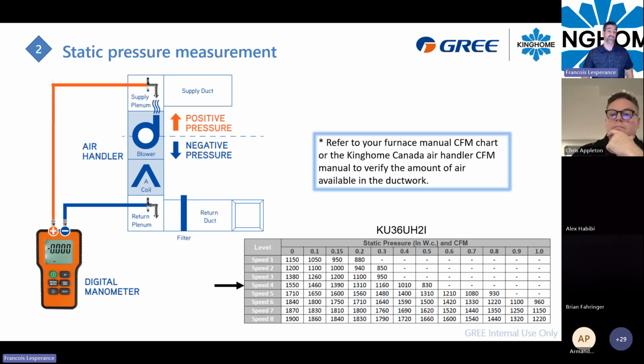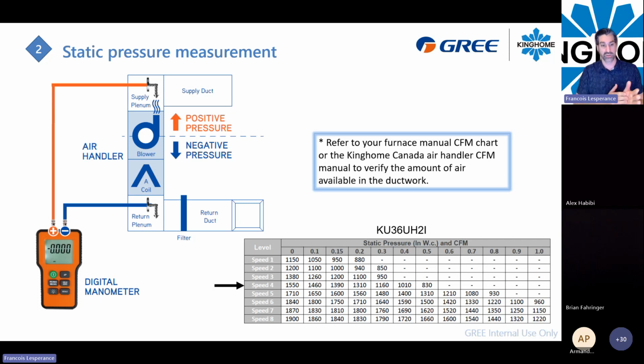Yeah. Well, 400 CFM per ton is, for me, the maximum you can use, because you want to make sure that the air makes enough contact with the fins of the coil to take all that temperature differential in the coil. So by reducing your airflow just a little bit, somewhere between 350 and 400, the system will work perfectly at that point.